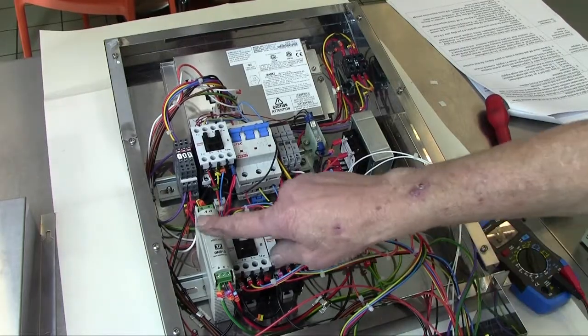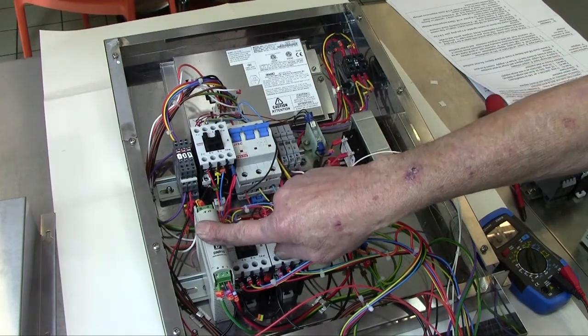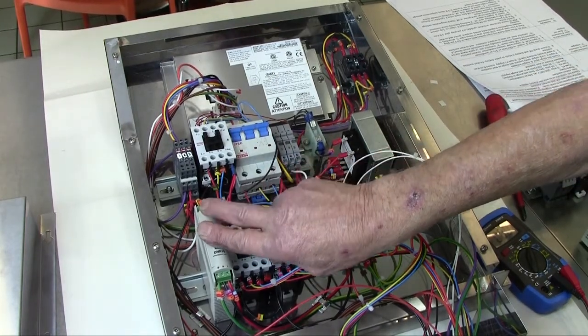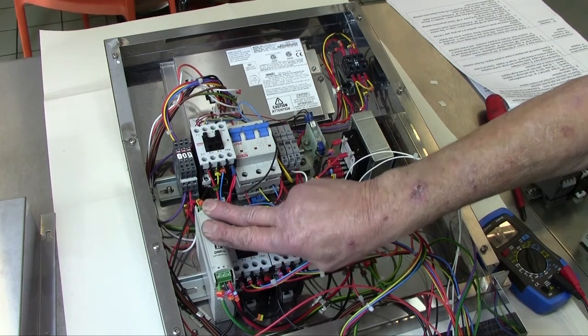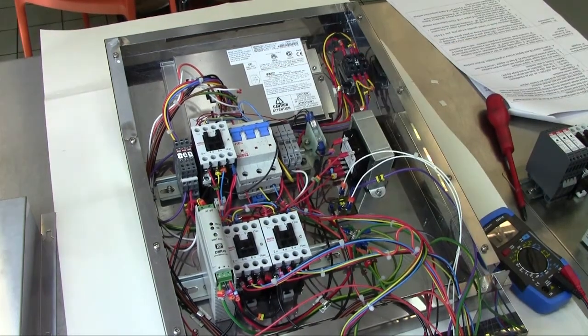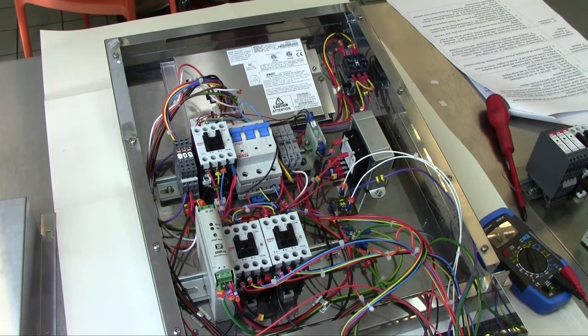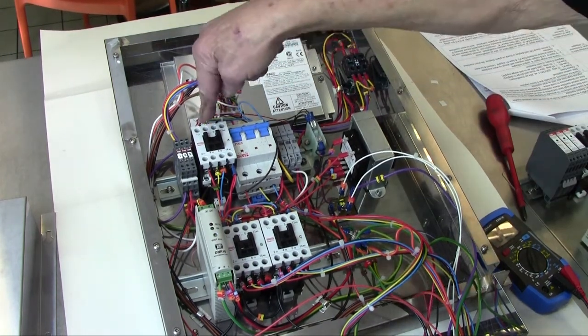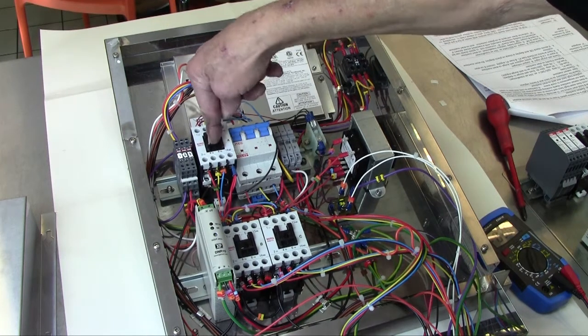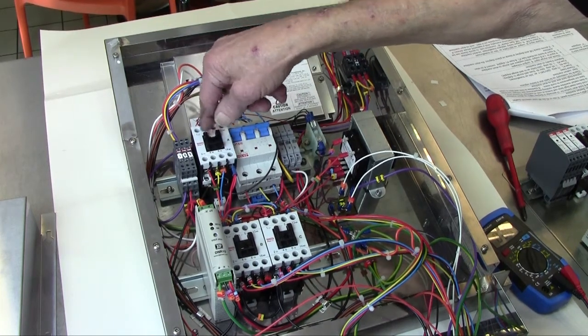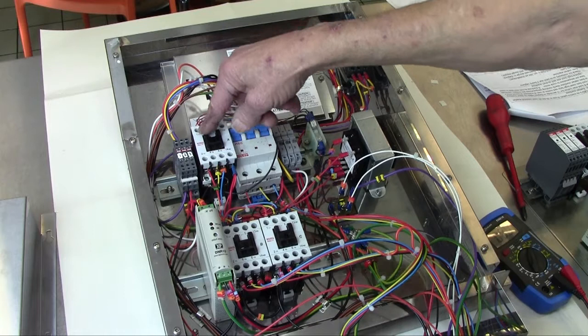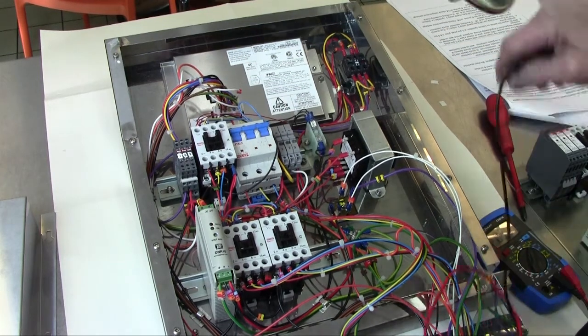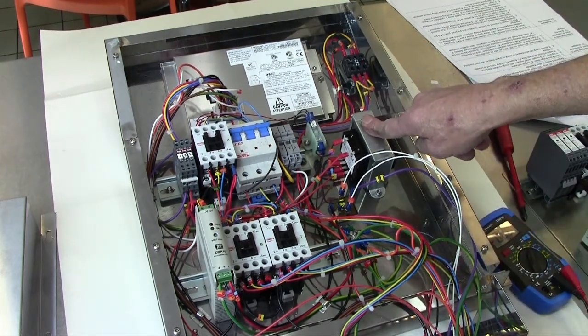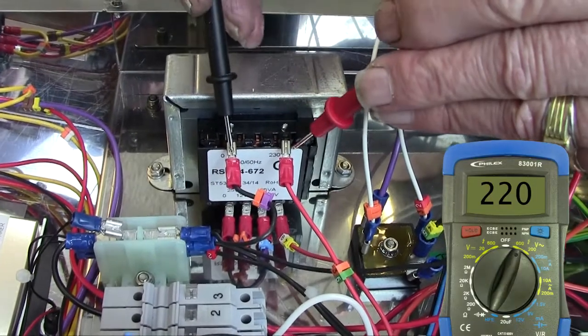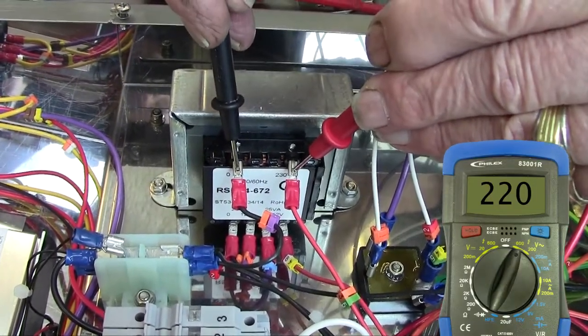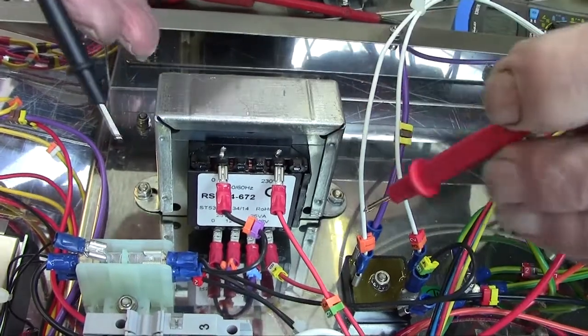If the checks on the anti-surge were okay, the input was okay and the output was okay, then replace the control panel. If the machine fails to start and a contactor, which is this, does not engage, usually an audible clack is heard. If it doesn't engage, then check the voltages on the transformer. The input voltages are 220 to 230 volts.